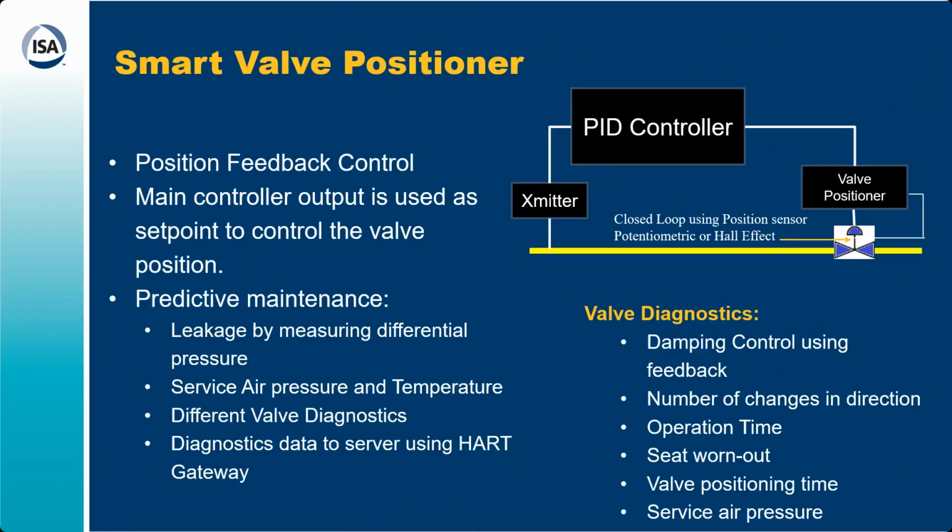Another is the valve positioning. As you know, those control valves are a very costly asset. Plus, control valves are employed in the plant, actually controlling the processes. So you have the PID controller and everything, but the actual control takes place in the control valve. So what should be the control quality? Your control quality gives you the quality of your process, the quality of your entire product.